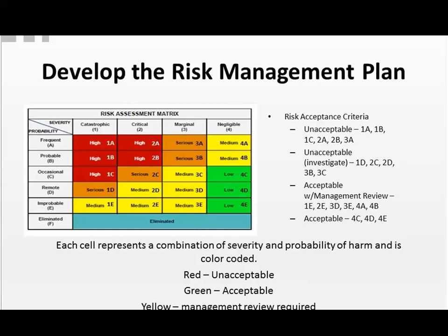Now, some risks by nature are more risk tolerant than others. For example, we can have a device where the team agrees that any risk that is in the red or orange cell can move forward in the risk management process. The rest remain in the watch list and are accepted. Now, in the 2012 version, all risk must be evaluated. Another device, in terms of what we've just indicated, would have a different criteria.